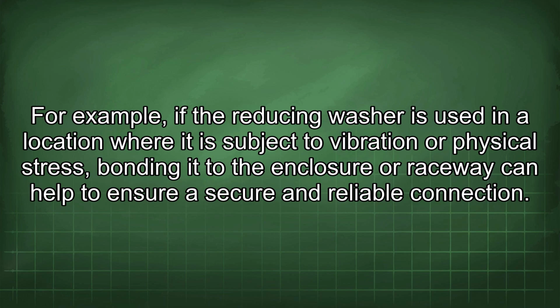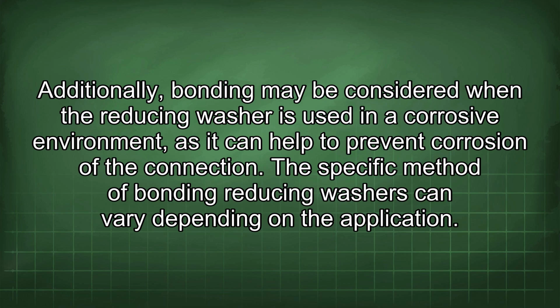For example, if the reducing washer is used in a location where it is subject to vibration or physical stress, bonding it to the enclosure or raceway can help to ensure a secure and reliable connection. Additionally, bonding may be considered when the reducing washer is used in a corrosive environment, as it can help to prevent corrosion of the connection.